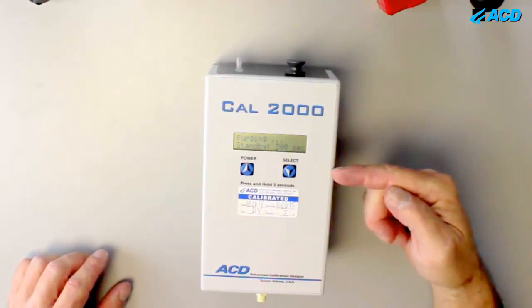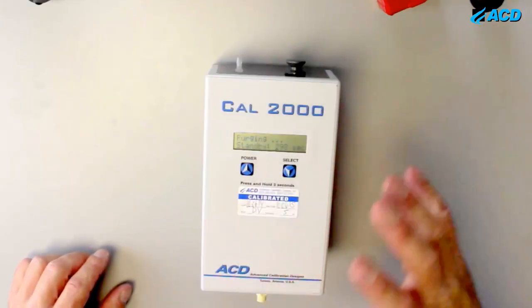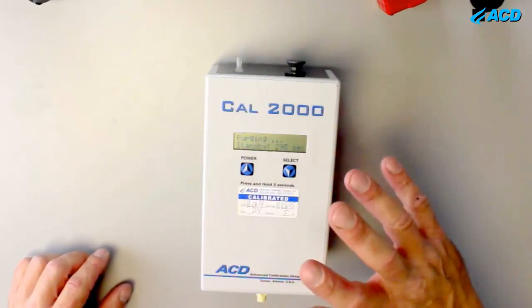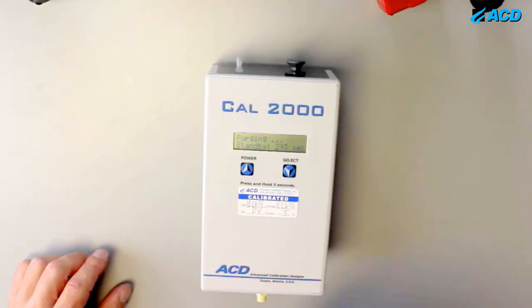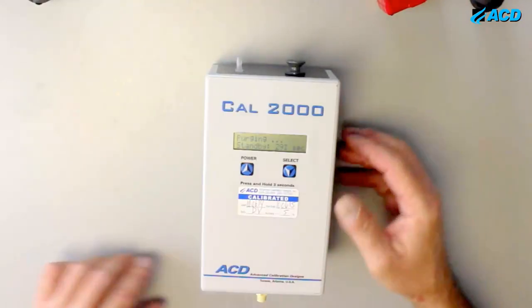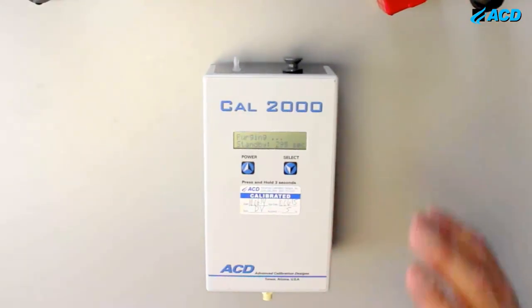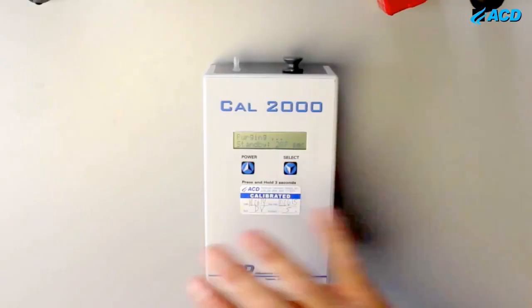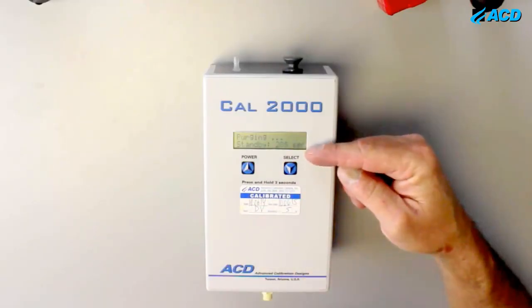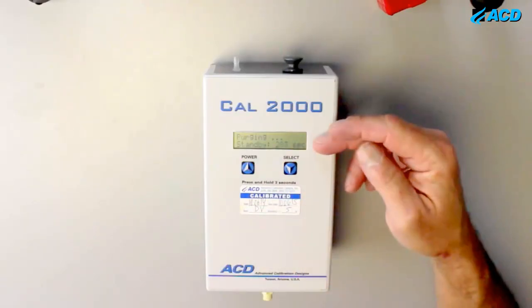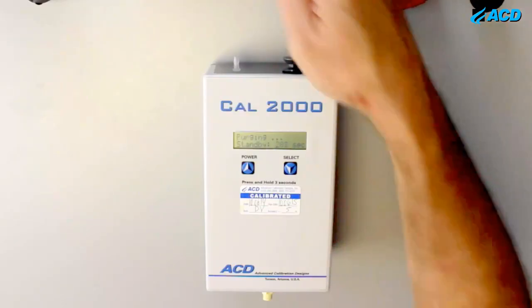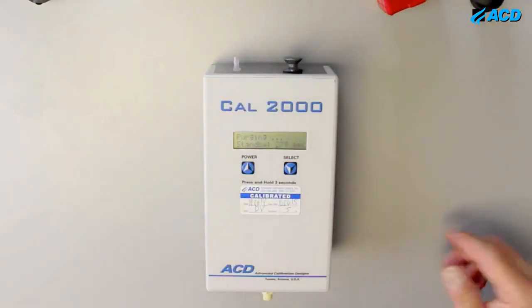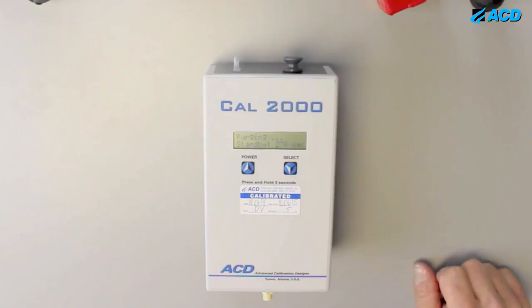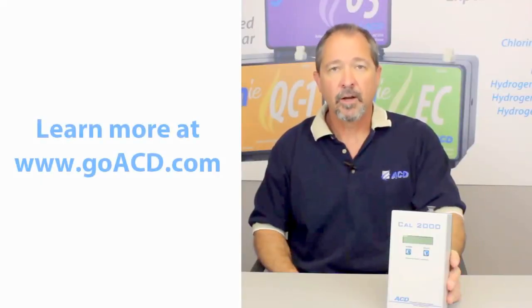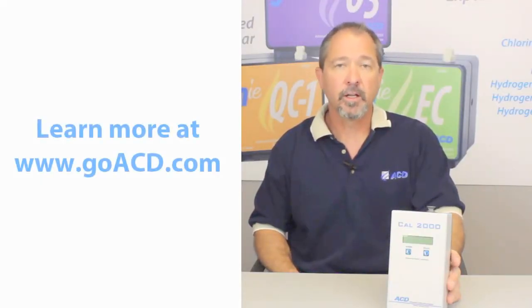Then the unit goes into purge mode. The reason it does that is simply to get all of the corrosive gas out of the system. Everything we make is corrosive and nasty, so you want that out of the system. So you're done. You can walk away from this, and in 5 minutes it'll be off. It's not generating any gas, it's just pulling ambient air in and shooting it out to get all the corrosive gases out of the system. And there you are. Now you know everything you need to know to correctly operate a Cal 2000 gas generator.